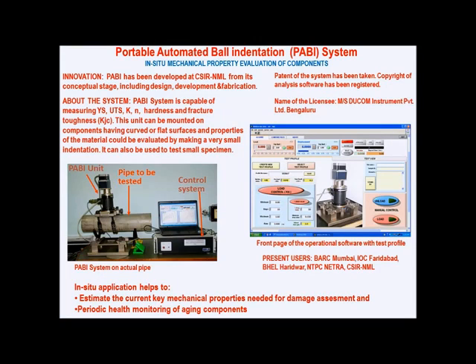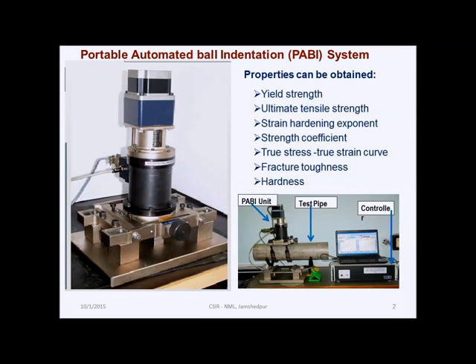It may be put on pipe with chain system and can be tested from any direction. For flat and other components magnetic shoes can be used to put the PABI system on the components.